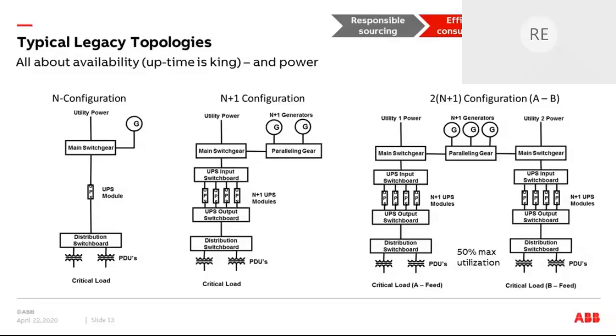What that allowed us to do is have both dual utilities, fed from generators on each side, N+1, so dual UPS banks, and then downstream a dual corded load. Critical load A and critical load B would feed into the UPS or into the computer room, so each server could be fed from utility 1, utility 2, or the generator bank. This led to a lot of very high availability. Tier 4, I believe, has downtime calculated to be just a few seconds a year, barring normal maintenance and things.